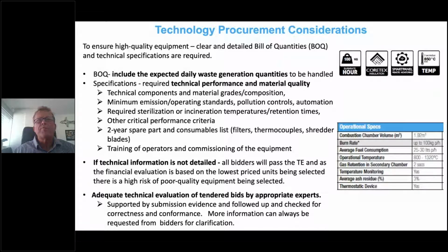You also need to outline sterilization or incineration minimum temperatures and any retention times, such as in the secondary chamber, and other critical performance criteria, such as whether you want a control panel with analog switches or a touch screen panel. This depends on your location, and whether you can fix things easily if they break down—analog tends to be more fixable than digital.